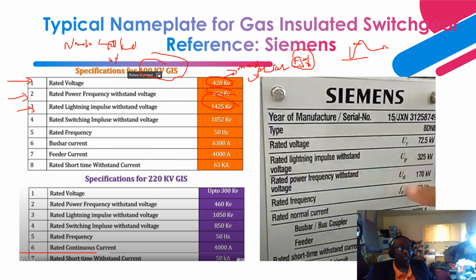Next is the switching impulse surge, right? During opening and closing of a circuit breaker that is in close proximity to the GIS, or internally if you are opening and closing the GIS, it emits an overvoltage condition. And this is how the insulation system and the components of the GIS have been built to withstand. This is how much voltage they can withstand.